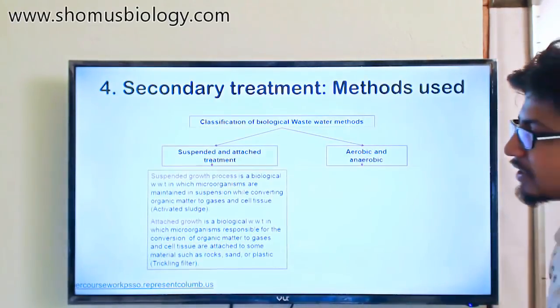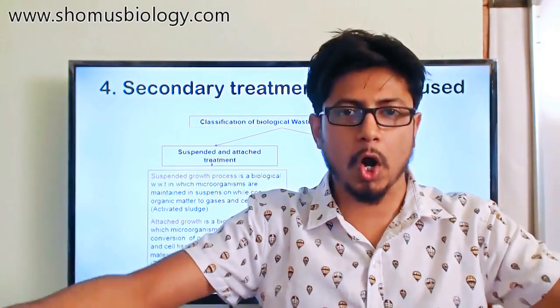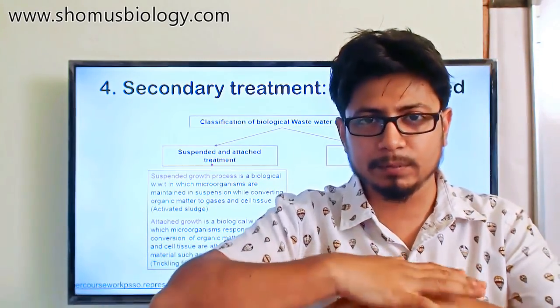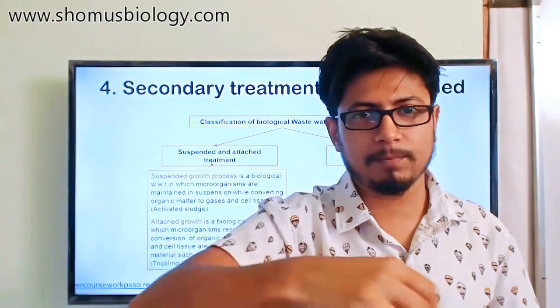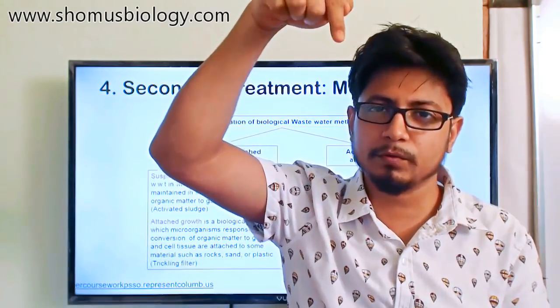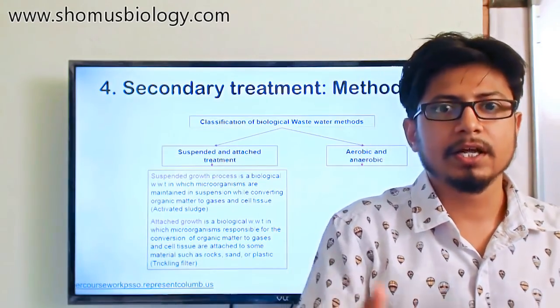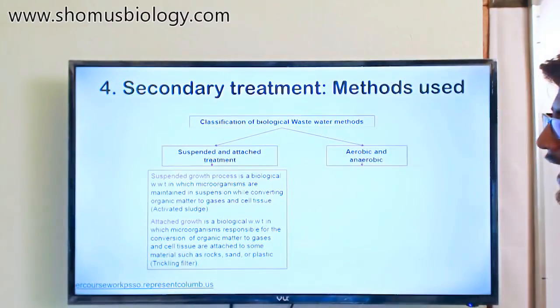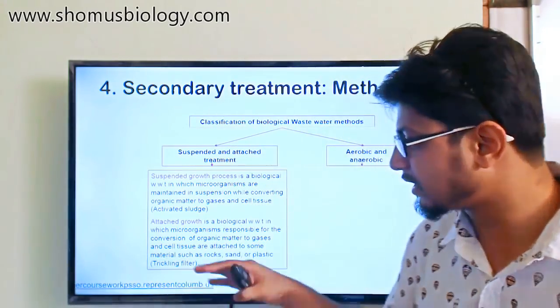Attached growth is when we use a large bed made with rock or solid particles, and on top of that solid bed bacteria, fungi, and protozoa produce a biofilm. We sprinkle water on top of that biofilm so that it receives nutrients, and the water continues moving from the top of the biofilm to the bottom of the solid surface, where it is collected and transported to the next stage.